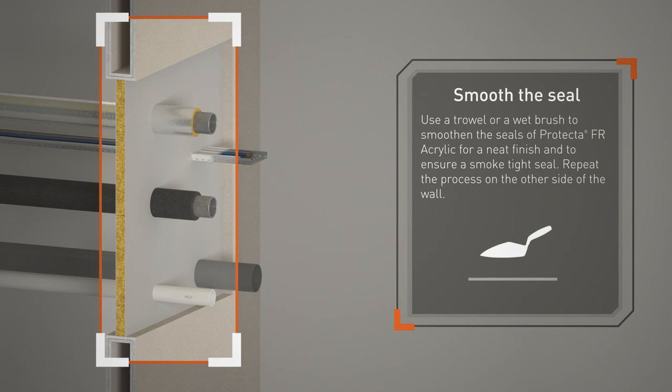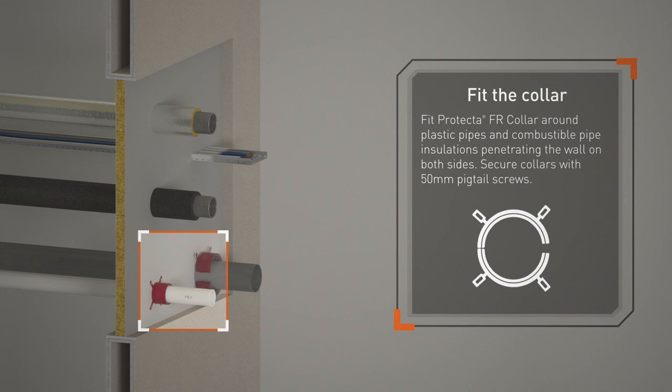Repeat the process on the other side of the wall. Fit Protecta FR Collar around plastic pipes and combustible pipe insulations penetrating the wall, on both sides. Secure collars with 50mm pigtail screws.